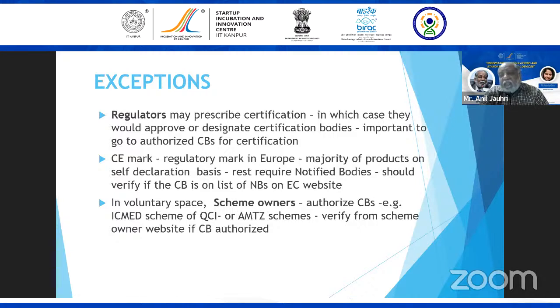So the best thing is to go to the scheme owner's website and verify whether a certification body is authorized or not. If somebody is coming to you and saying, I'll issue you ICMED certification, please go to the ICMED website and see whether that certification body is listed there. If somebody says, I'll issue you a CE mark certificate, go to the European Commission website and see whether that body figures in the list of notified bodies. If somebody says, I'll issue a certificate for the Food Authority, go to the Food Authority website and see whether that body is listed. Or if somebody says, I'll audit on behalf of CDSCO, go and see whether it's a listed body. So these are exceptions.